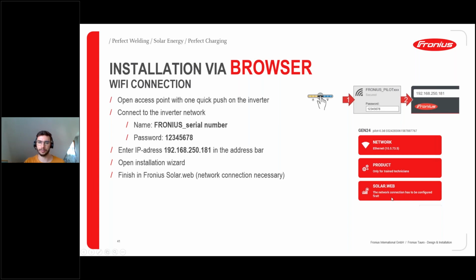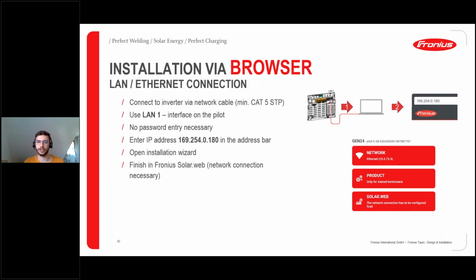However, there's even a 3rd option you can choose, which is a LAN connection. If you want to use a direct LAN connection to your laptop, just open the device and connect your LAN cable to the LAN 1 port. Make sure to always use LAN 1, because LAN 2 is only used internally and not meant for the commissioning process. After setting up this LAN connection, we again open Google Chrome, type in the IP address, and follow the same steps: network, product, and SolarWeb. Then we're done with the commissioning.